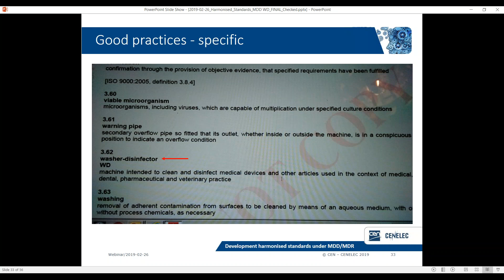There is a definition in the standard of a washer disinfector, and it's a machine intended to clean and disinfect medical devices. So it's clear that it's not a medical device as such. And perhaps that standard can be very useful. However, a role of harmonization of a particular standard is to enable a manufacturer of a medical device to benefit from presumption of conformity. So a manufacturer of the machine which is intended for cleaning and disinfecting medical devices can be, as I said, a very important element of the whole process, but its manufacturer does not really have to comply with the MDR or IVDR or previously the directives.